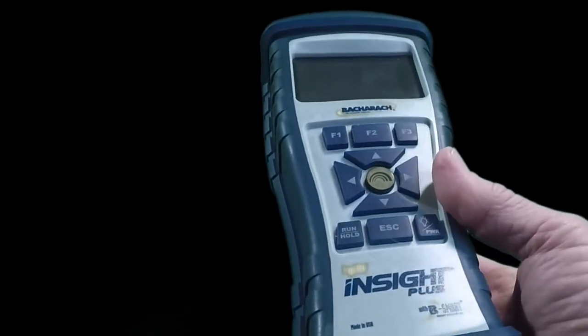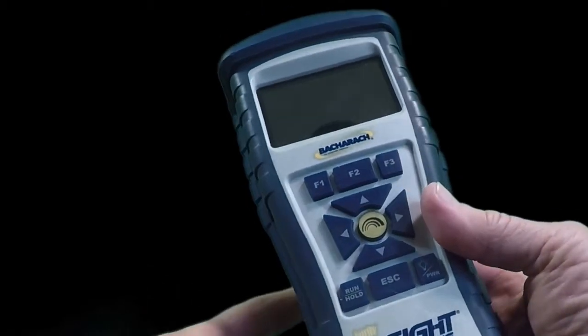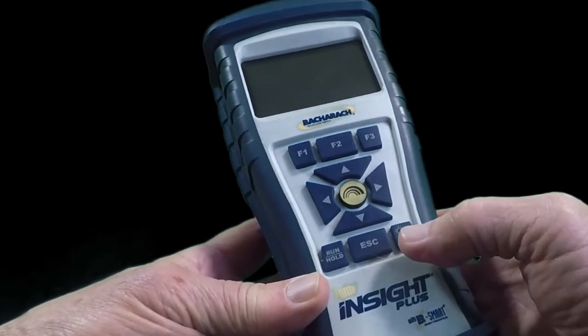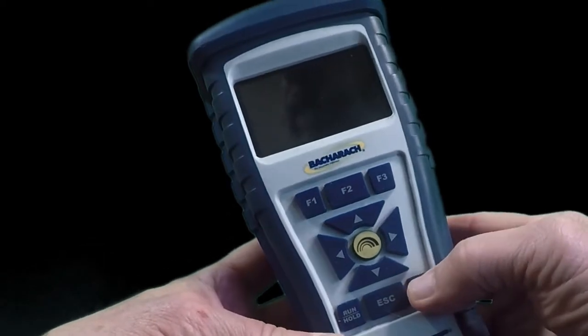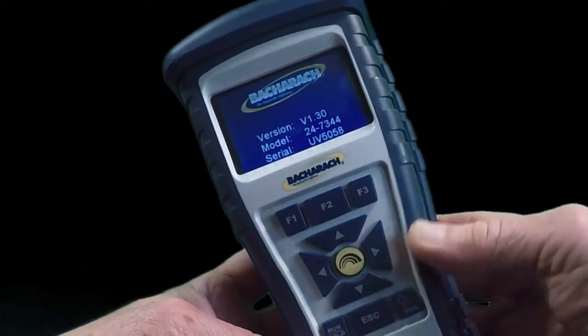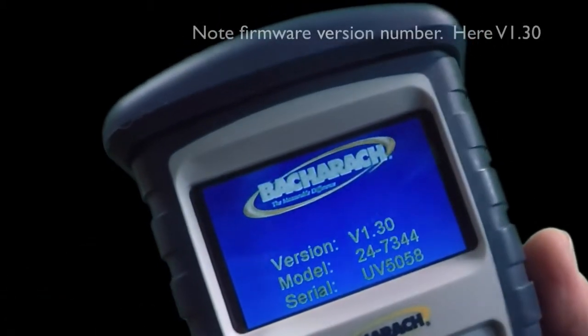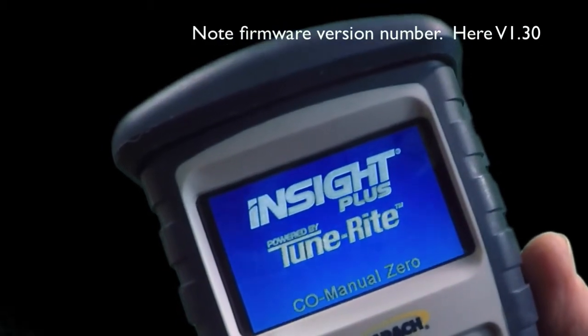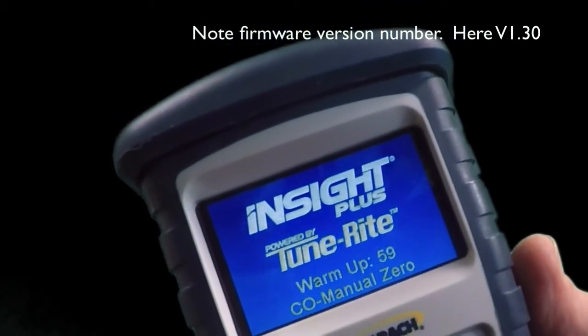Okay. Make sure that the instrument is not pulling flue gases when we turn it on, as it is allowing the sensors to stabilize at this point. So we'll go ahead and hold the button down for a second or two. First thing you'll notice in the display is the version number. It's 1.30 if it went by too quick.